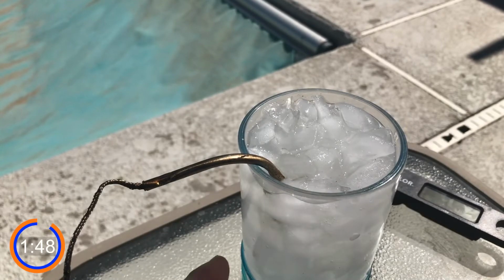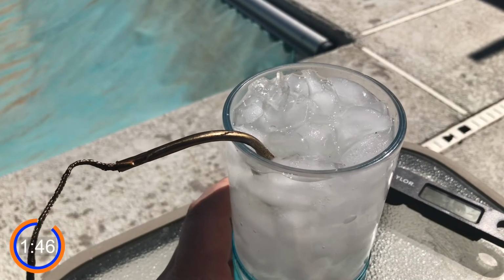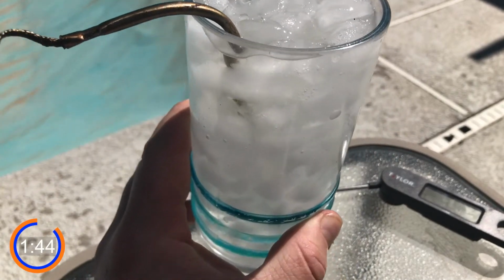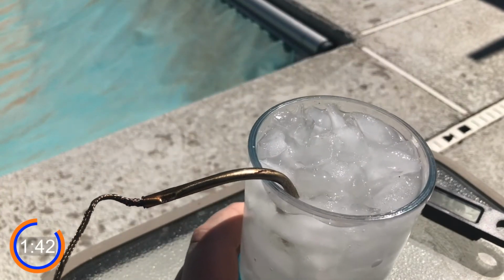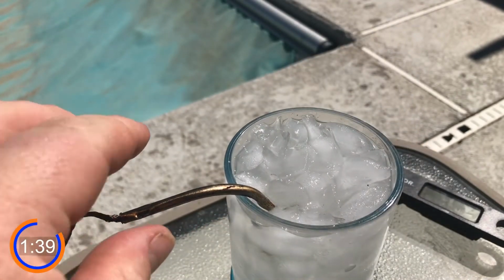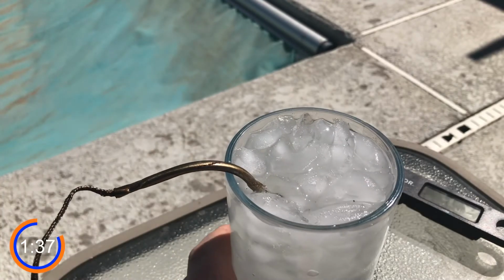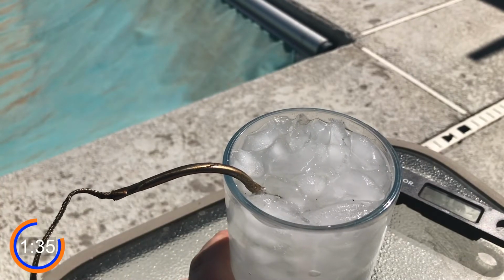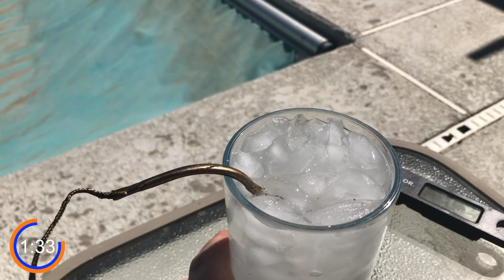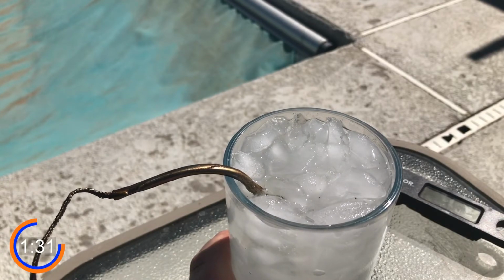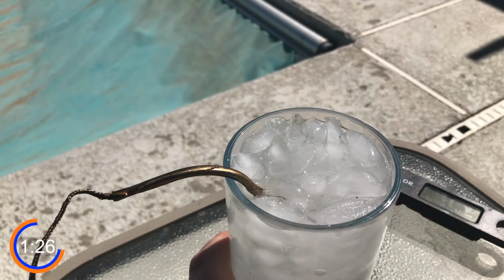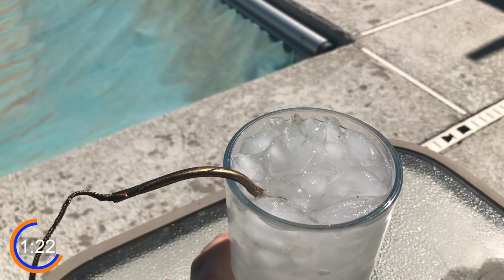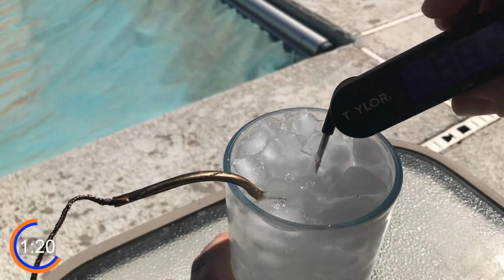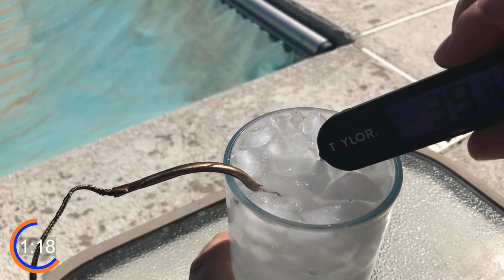So what I've got is a glass of crushed ice here. It was filled to the brim with crushed ice. Then I filled it to the brim with water. And as you can see, this glass is deep enough to allow my entire thermometer, or as much as possible, to be submerged into the water. And we want to make sure we let this sit for at least 1 minute. I've had it in here for a couple minutes while I've been getting everything ready. And we can go ahead and see what we're looking at here, if it's dark enough.